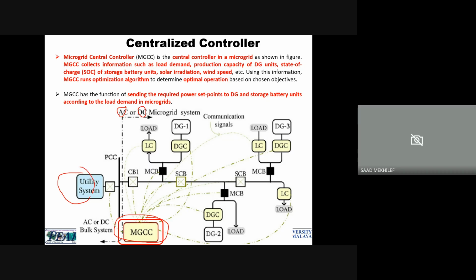So the central controller makes decisions based on resource availability - for example, the state of charge of batteries. We have limits on how much we can charge or discharge the batteries. So for example, if the state of charge is 20%, we cannot discharge it further. But sometimes, if we have critical loads, we may be able to discharge further. This has to be coordinated inside the master control.